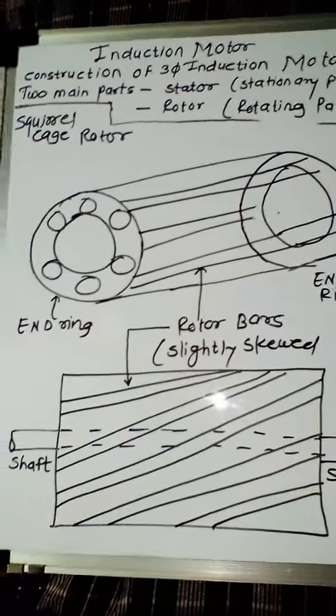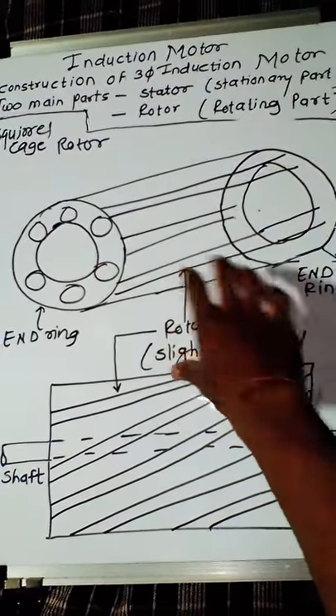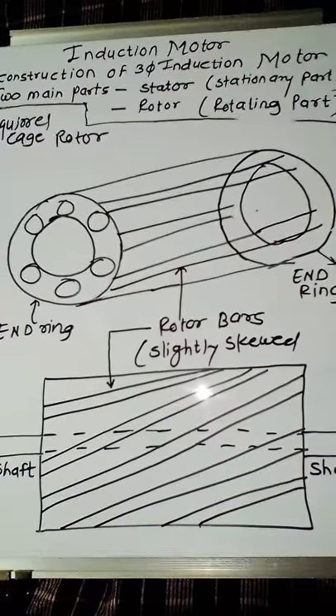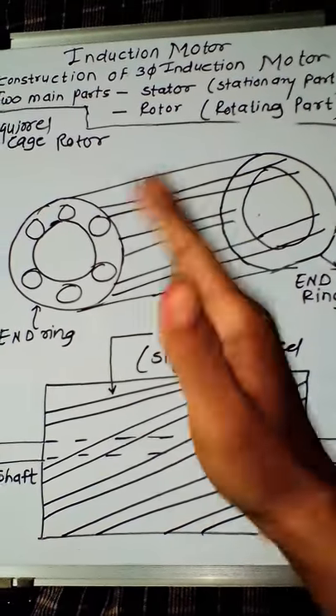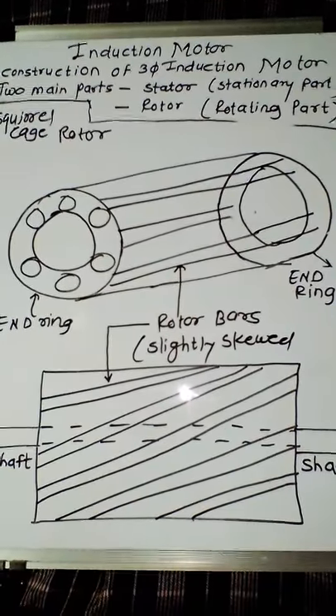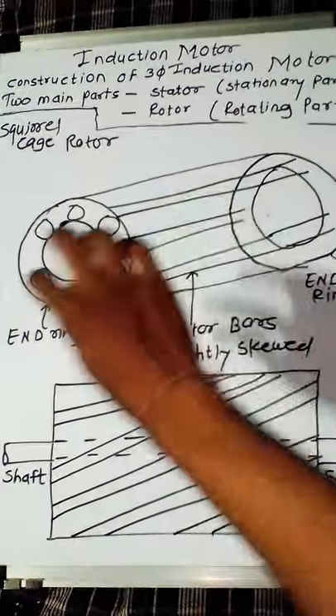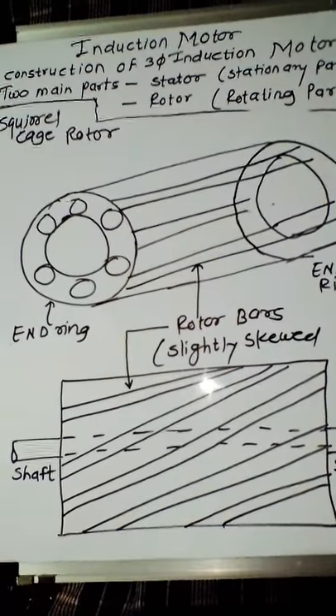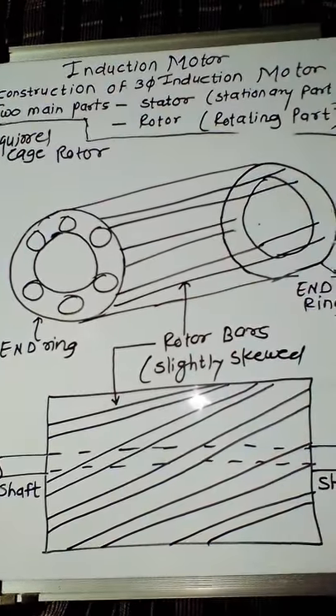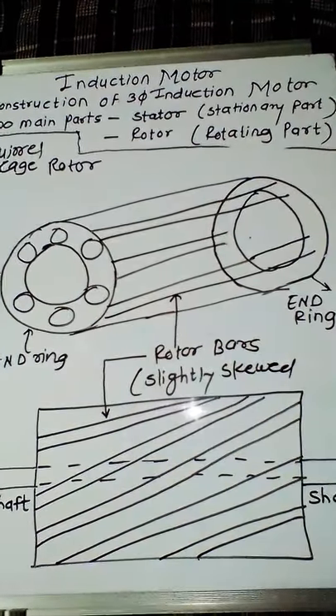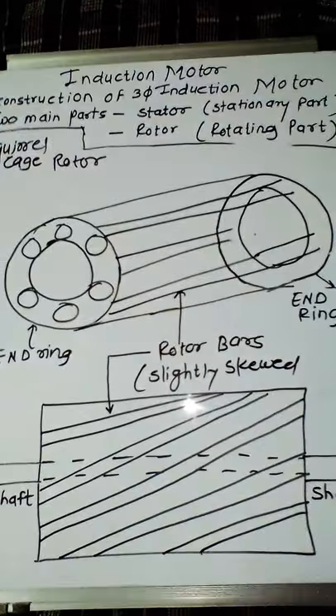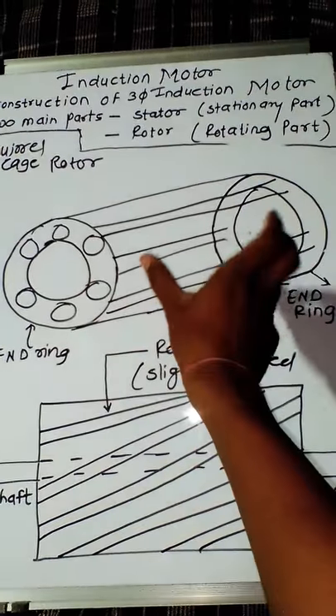The squirrel cage rotor consists of a cylindrical laminated core, as you can see in this diagram. The laminations are insulated from each other by means of varnish, and these laminations are slotted to carry the rotor bars. In the squirrel cage rotor there is no rotor winding — instead there are rotor bars made of copper, aluminum, or alloy. These bars are placed in the rotor slots and form the rotor winding.